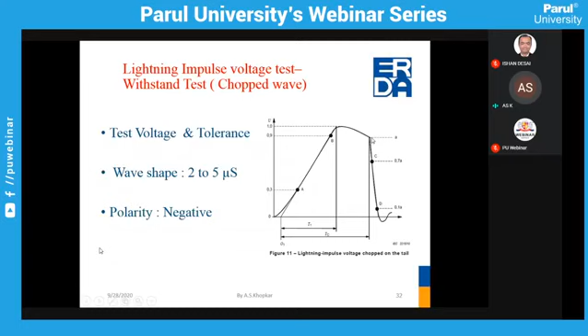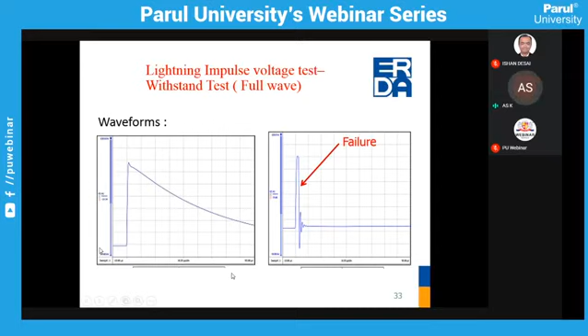After reaching peak, gradually it falls to 0. If such type of waveforms we get, then we can say the product is passed in the impulse test. But here you can see after reaching peak, suddenly voltage collapses. The voltage drops back to 0. So this is the indication of the failure. By studying the waveform, we can tell whether the product is passing or failing. This is only one example I have taken. There are many examples of waveforms which represent various types of failures.